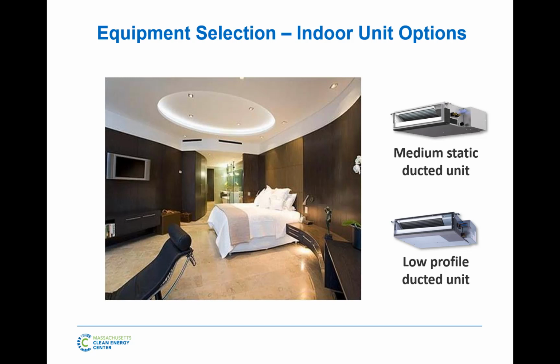So a common one would be our low-profile ducted unit. Low profile, so they're under 8 inches tall, but because they're low profile, they can't handle as much ductwork. So they're very common for a hotel like this. Put your low-profile static unit right at the doorway, above the bathroom, whatever it may be, a couple feet of ductwork, then the air is delivered to the space. Pretty common, works very well. Then a step up from that, you have a medium static, so a medium profile unit, which can handle significantly more ductwork, but it's also 2 inches taller. So this is kind of the standard unit that'd be used for a space like this. You can put a ducted unit right in the middle of this room, duct to all sides of the room, and there's plenty of static pressure to handle that.